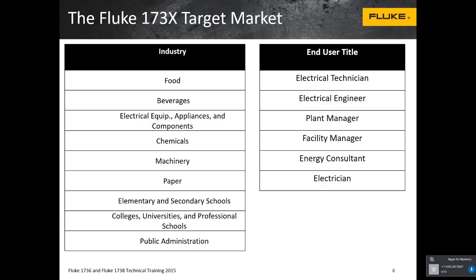There are some guidelines for doing load studies. NEC 220 would be one of the guidelines that gives you basically allowance for doing up to a 30-day load study. There's also a 1-year provision, but you can do a 30-day load study, and all 4 models will support that - they have more than sufficient memory to record that long.